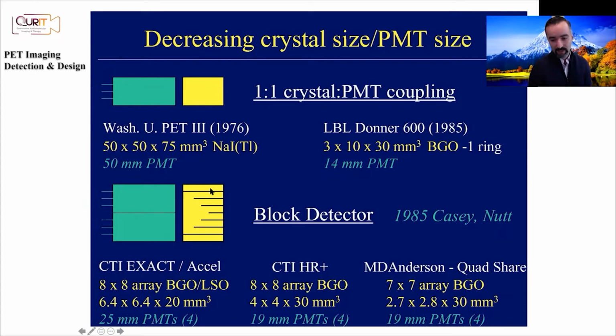But there was this really innovation that happened decades ago, very analogous, very consistent, same way of thinking as for Anger logic actually. So you would take a scintillator block, you would cut through it, and you could fill these spaces with reflective material that reflects scintillation light to maintain it within this space. But then using Anger logic, as we've talked about, if you have an event, let's say a gamma ray comes here. This gamma ray results in scintillation photons. These scintillation photons, some of them end up here, some of them end up going here, some here, some here.